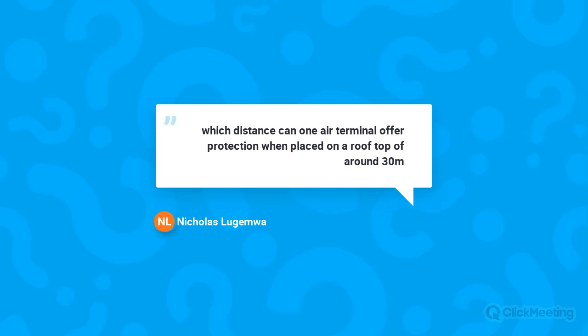So the last question: which distance can one air terminal offer protection when placed on a rooftop of around 30 meter? This is a very vague question. So this has to be calculated. Again, if you go back to the slides where we spoke about the rolling sphere method and the angle method, it's dependent on a lot of different things like the height and other buildings or structures in the vicinity to see if it covers or not. To know if it really covers, you have to do the distance or the lightning protection design and actually calculate it based on one of those three methods that I mentioned. But you're welcome to send it if you would like us to have a look at that as well.